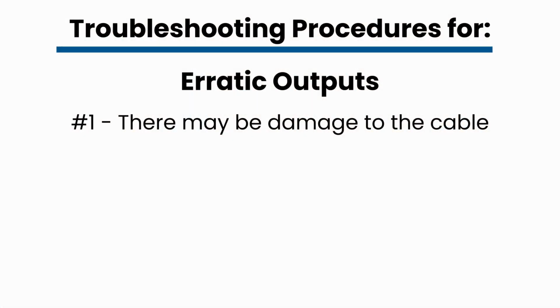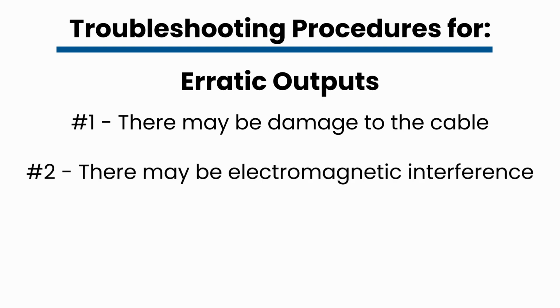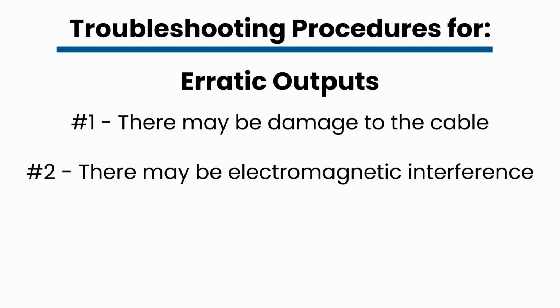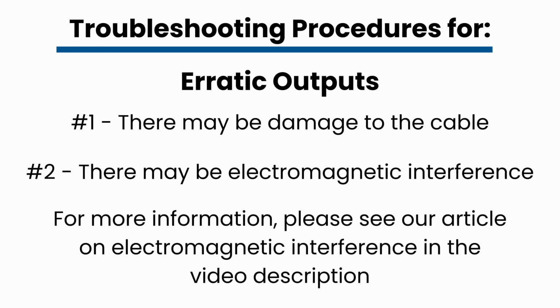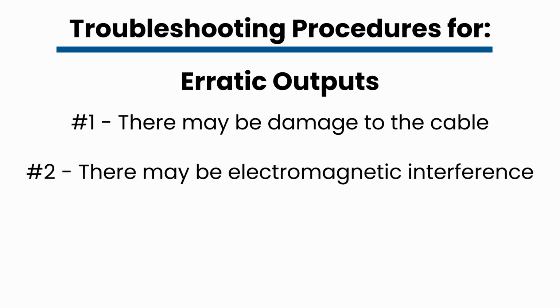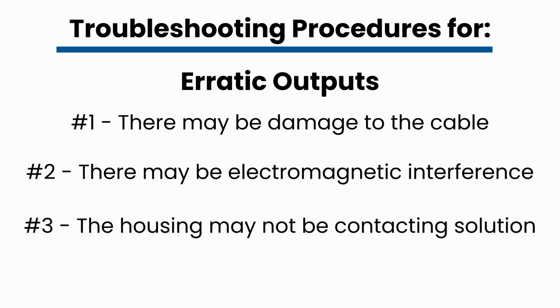Number 2, the sensor or cable may be close to a high power machine or wire that is outputting excessive electromagnetic interference. Check for any patterns that coincide with heavy machinery turning on or off around the sensor. Move the cables away from any areas of potential electromagnetic interference. For more information on this, please see our article on eliminating electromagnetic interference in analog systems. Number 3. The metal housing may not be in contact with the sample solution.